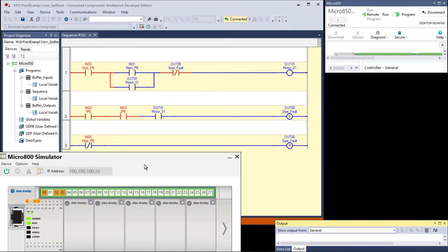Now, if we start, we'll go ahead and start. We'll double click on one. And you see that you instantly get a size fault. Now, notice that this rung is not true. In the previous code, the rung stayed true because we sealed it in. But you see, this is still on. The color of these instructions, all the instructions you find over here, denotes the state of the memory location, on or off, one or zero, high or low.